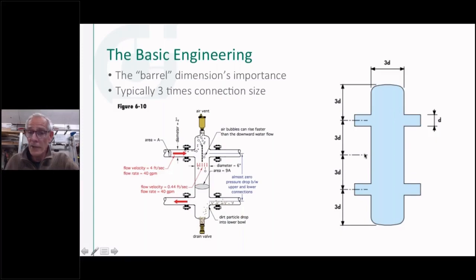Now, the other thing that's critical is the spacing between the tees, and here we just put some numbers to all this. So again, if you know the size of the pipe based on the flow rate that you want to run through it, then all these dimensions you can just calculate, because you could make your own. And I'll show you some examples of some homemade ones here, but I've seen ones where they've taken that 2-inch pipe coming into it and they used a 2.5-inch pipe for the center barrel. You're not going to have enough space in there to get that separation. Basically what's going to happen when one circulator is running, it's going to induce flow on the other side, vice versa, depending on which one's running. You don't have separation because you didn't put a big enough space in the road, so to speak, to establish that separation.